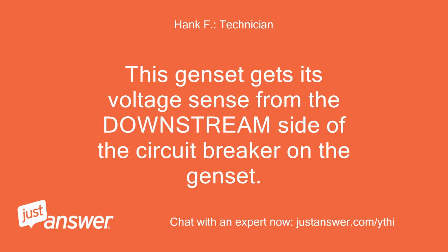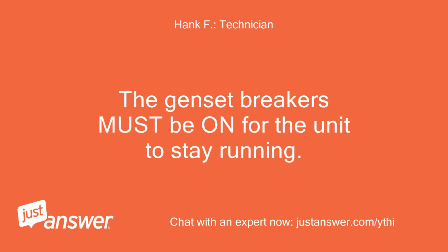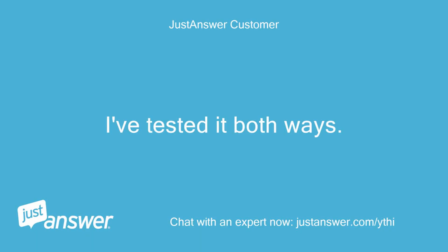This genset gets its voltage sense from the downstream side of the circuit breaker on the genset. The genset breakers must be on for the unit to stay running. I've tested it both ways.